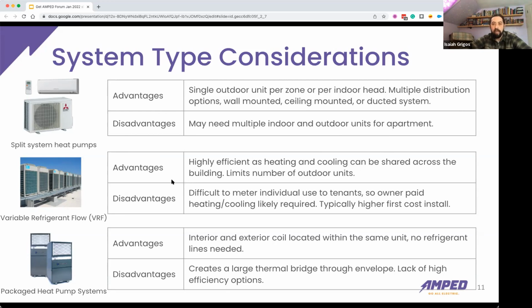And what it does is basically you have refrigerant lines that go from unit to unit to unit, with some branch controllers that send refrigerant where it needs to go. But basically, these outdoor condensers just move heat from the outside through refrigerant to various indoor units. And you can use whatever indoor units you want, whether wall-mounted systems, ceiling-mounted, or ducted. These are very efficient, but for multifamily buildings, you can't put the heating and cooling onto tenants, so it becomes kind of an owner-paid utility for the building.